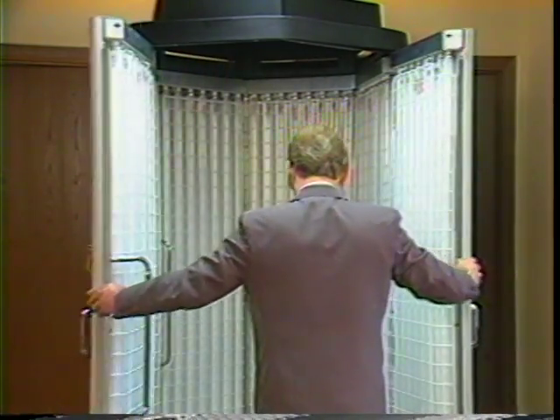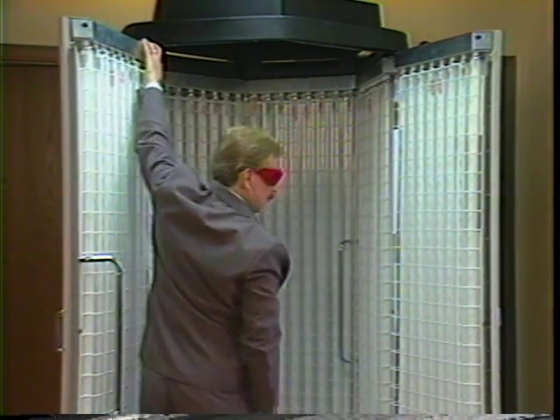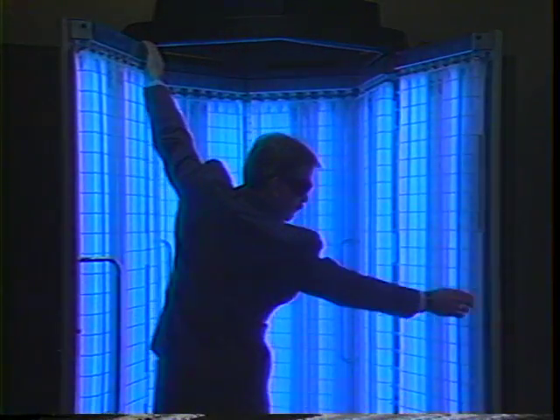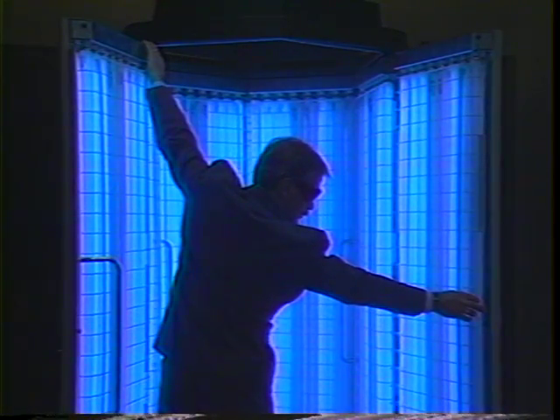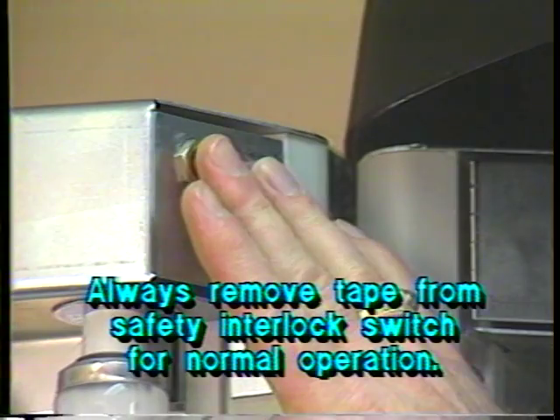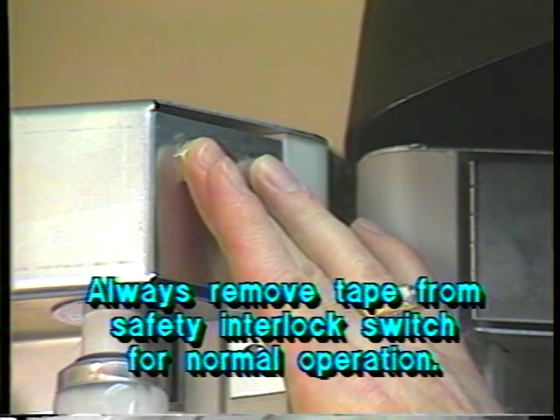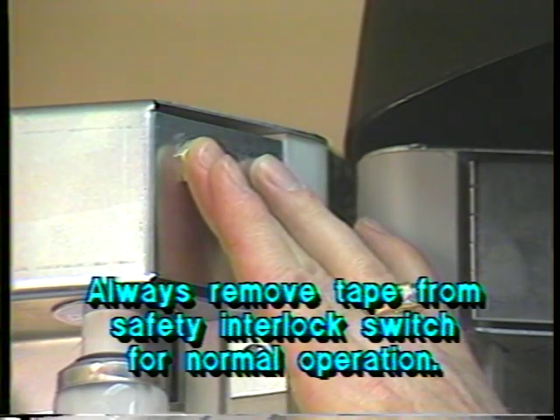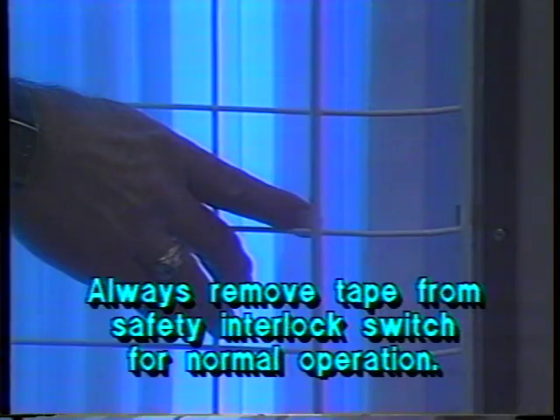Eighth, if a lamp is out in either door section, the operator must operate the unit with the doors open in order to view the out lamp and perform the necessary test procedures. To do this, the operator must wear eye protection and hold or tape the interlock switch closed while viewing the lamp section. Then follow the same procedures as we just discussed.